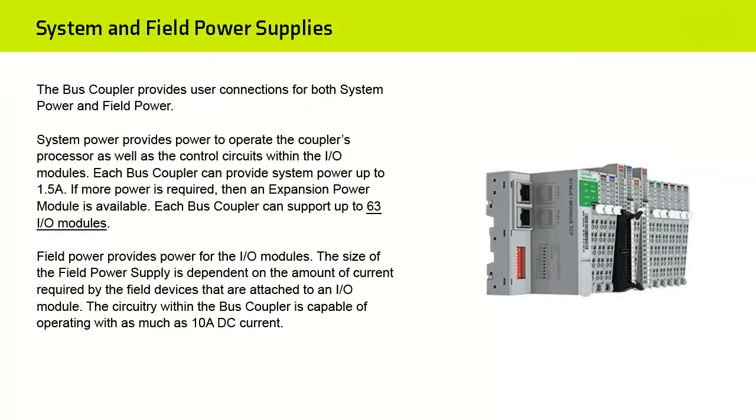The Bus Coupler provides user connections for both System Power and Field Power. System Power provides power to operate the coupler's processor as well as the control circuits within the I/O modules.